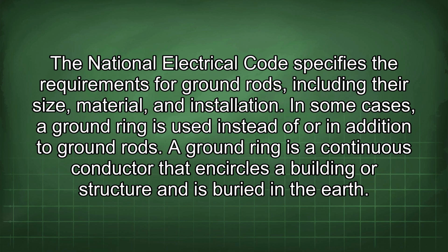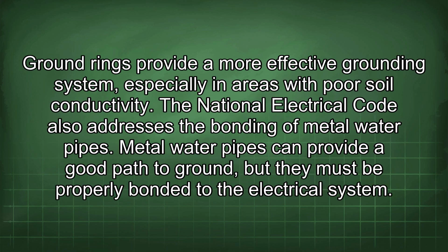In some cases, a ground ring is used instead of or in addition to ground rods. A ground ring is a continuous conductor that encircles a building or structure and is buried in the earth. Ground rings provide a more effective grounding system, especially in areas with poor soil conductivity.